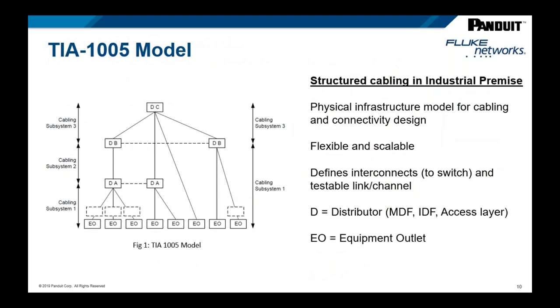TIA-1005A defines a basic architecture for the structure of cabling and connectivity in the industrial premises. Starting at the bottom, EO stands for equipment outlet. There are two and sometimes three sets of patching systems or distributors — depicted as distributor A, B, and C — on the way up to the network core at the top. Distributor C and its patch panels would be co-located with the actual network core equipment in a telecom room.